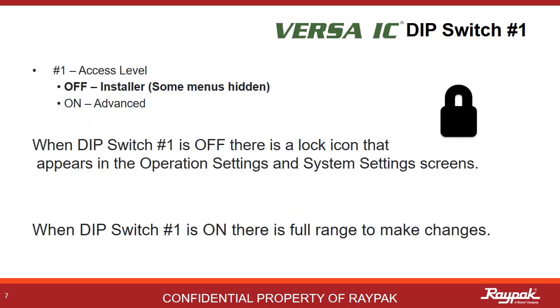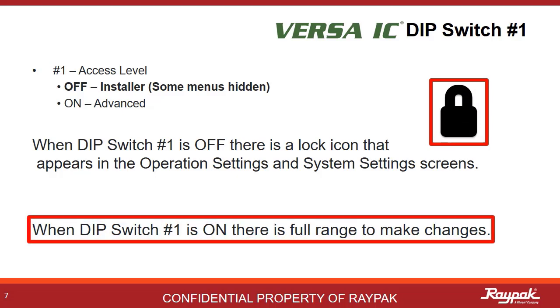Dipswitch number one is a limit switch for the access level. This comes in handy when there is the potential for untrained hands working on the equipment. When the access level is limited, the lock icon will show on some of the screens. Turn Dipswitch number one on to regain full menu access.